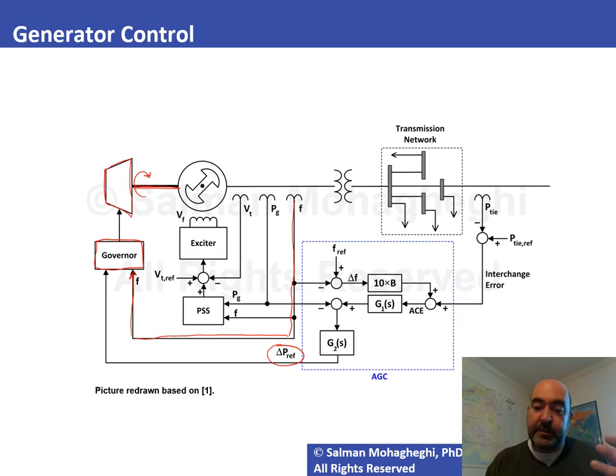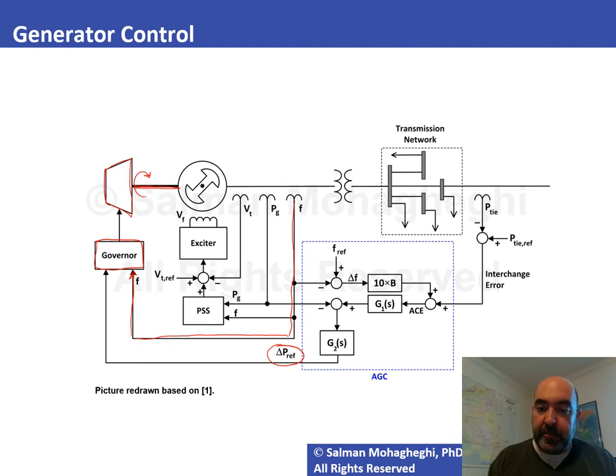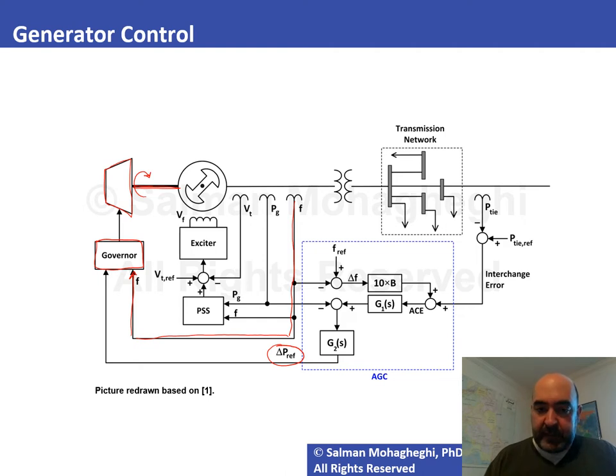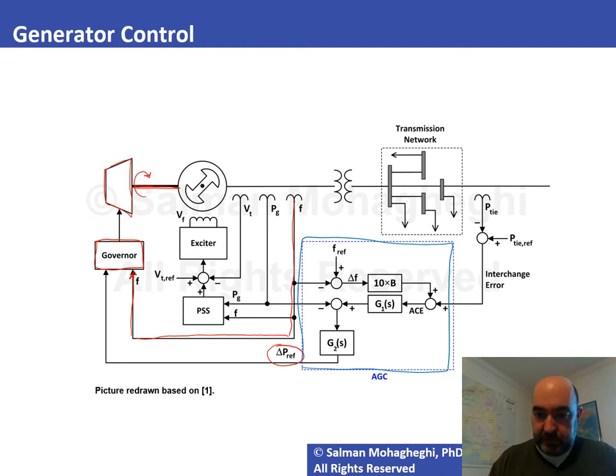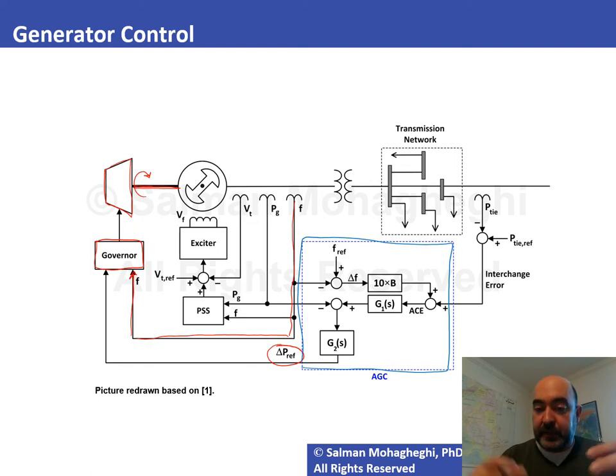If Δ P_ref is positive, the generator is forced to inject more power into the grid; if negative, it reduces active power output — both achieved by making the prime mover go faster or slower. This Δ P_ref comes from the AGC (Automatic Generation Control) system, which looks at frequency deviation from the reference value of 60 Hz and also monitors scheduled power transactions through tie lines connecting different systems.